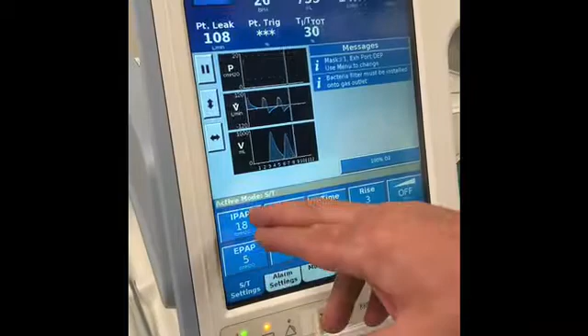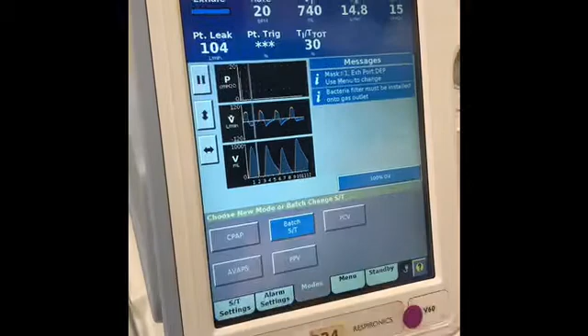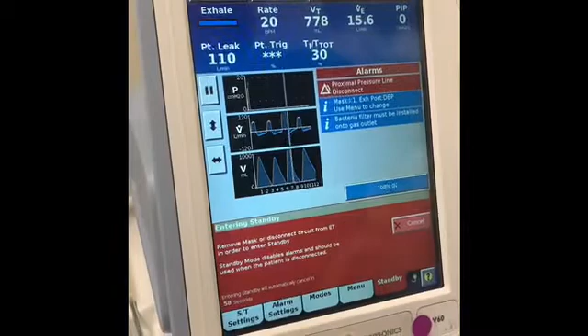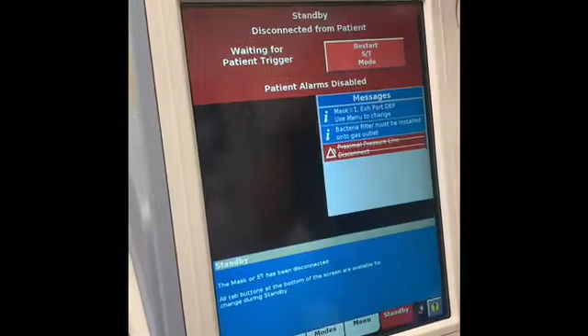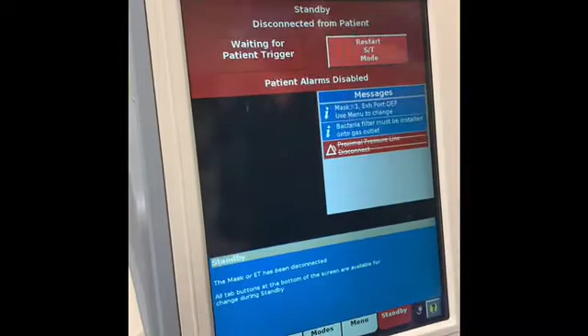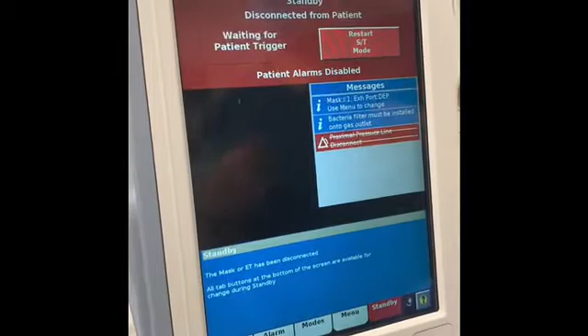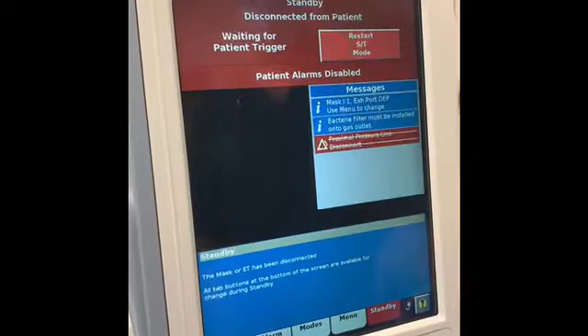So right now we are in active ST mode. So we're going to change the mode. So actually let's put it in standby. If you put the machine in standby, it does this automatically. So everybody, please be aware that if it's in this mode, it's disabled. The machine is in standby. So make sure that if you're going to put the patient on, you take it off standby, because this may be deceptive in a sense that you see a screen, but the machine's not doing its function. It's just sitting there in standby.